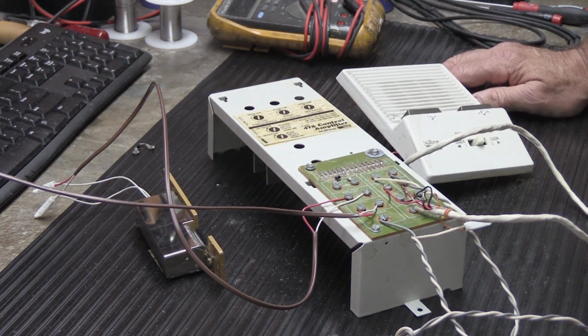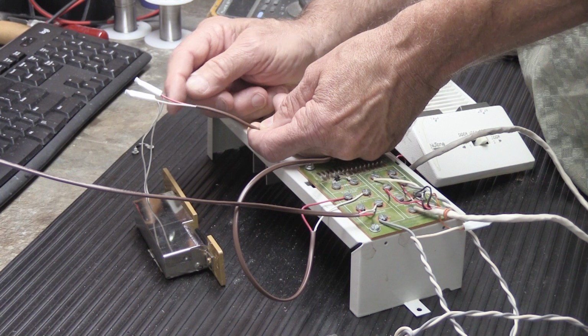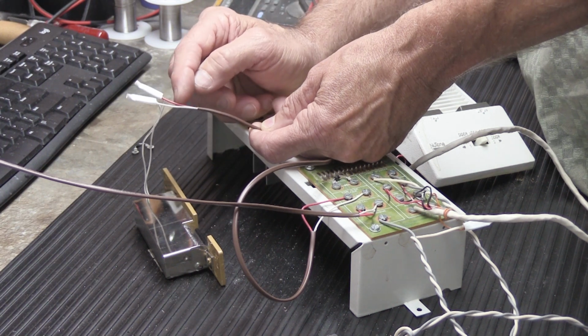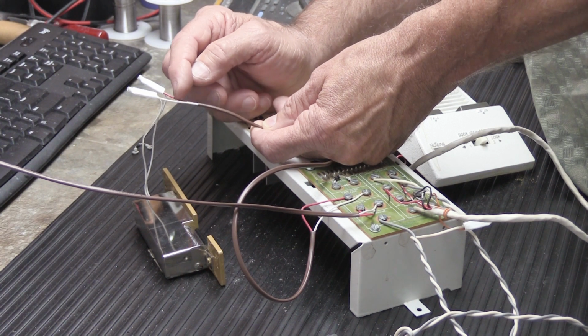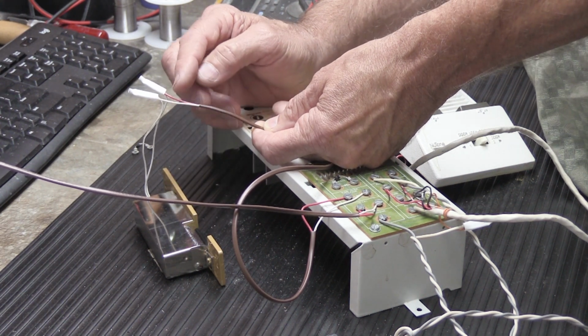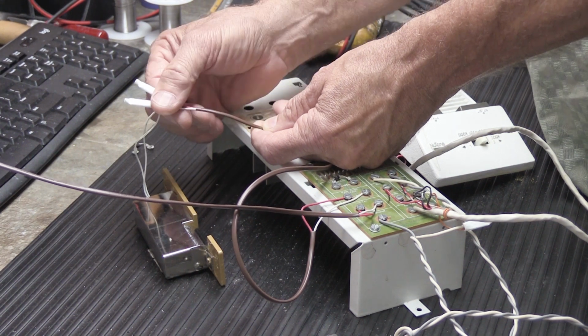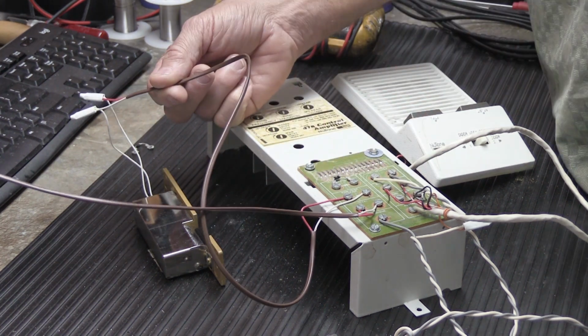Wiring problems do occur. We had a building that we took care of for decades, and suddenly one day something went wrong. I don't know exactly why it happened, but there was a short in the wire right here near where the door release was mounted in the aluminum storefront frame, and it shorted across the aluminum, and it created a situation where the door release wouldn't work. We repaired the short, put some tape and insulating over it to protect it, and then it all worked great. So it could be something as simple as a wire.